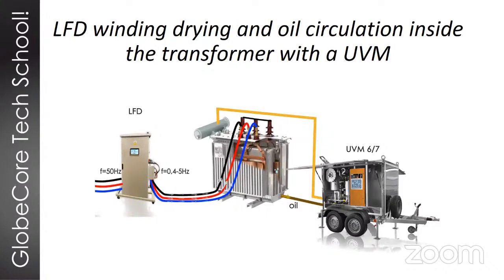We can also combine the LFD with the UVM or CMM oil processing system. And the system here works like this. So we heat the windings with an LFD. The moisture from the solid insulation migrates into the oil inside the transformer. And then the thermal vacuum drying and filtration system, like a CMM or UVM, reduces that water content, removes that water from transformer oil, and it also degasses and filters the oil. And this cycle can be run again and again until the moisture content in the oil drops to 10 ppm or below. This usually happens when the windings are heated to about 75 degrees Celsius. Next slide, please.